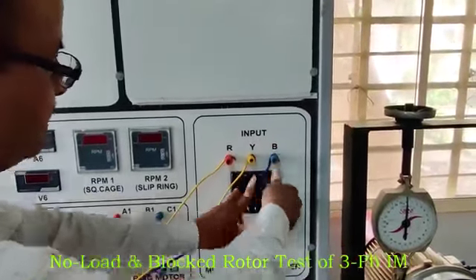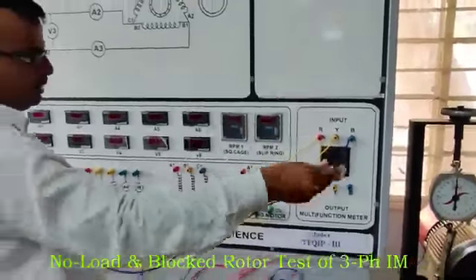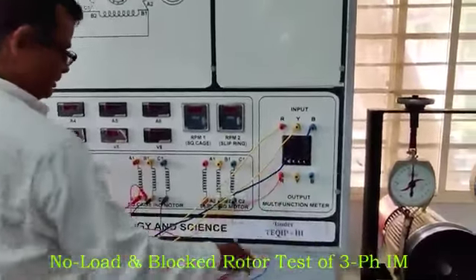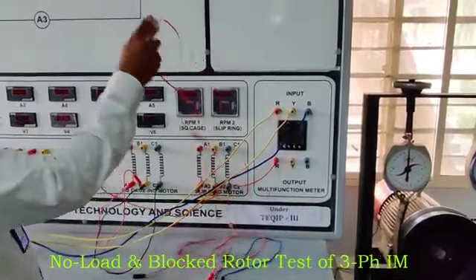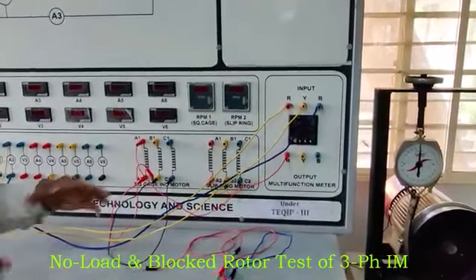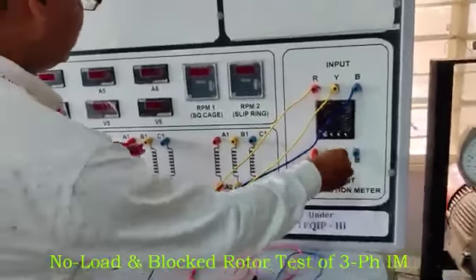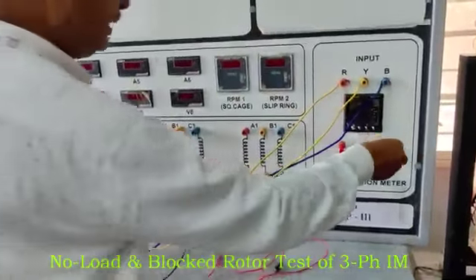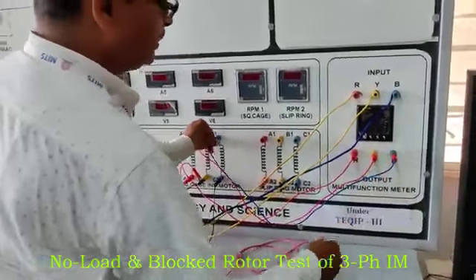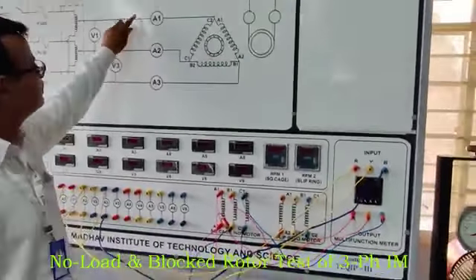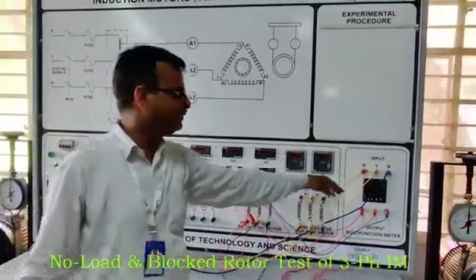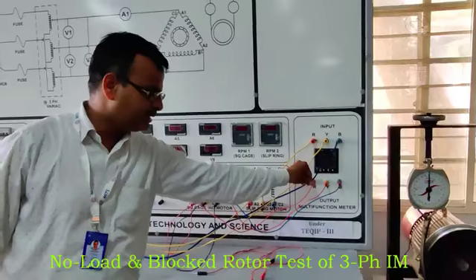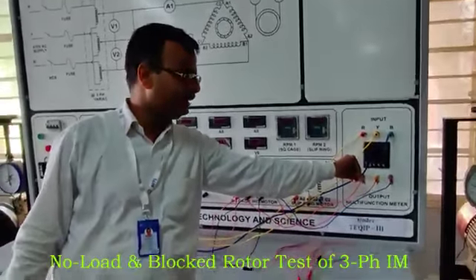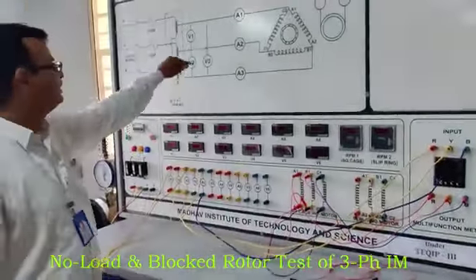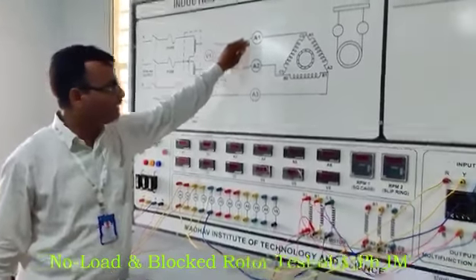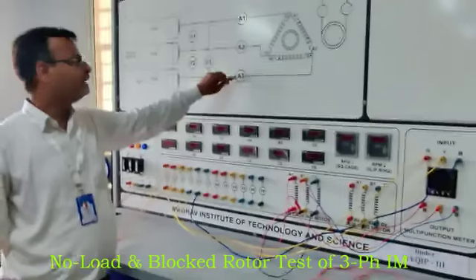And the output terminals of this multifunction meter connect to the stator terminals: R connects to A1, Y connects to B1, and B connects to C1. So a multifunction meter is attached in those positions. The multifunction meter will measure the no load input power and no load power factor. And these are A1, A2, A3. These are connected in lines, so they will measure line current.